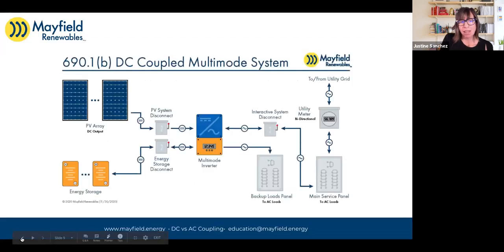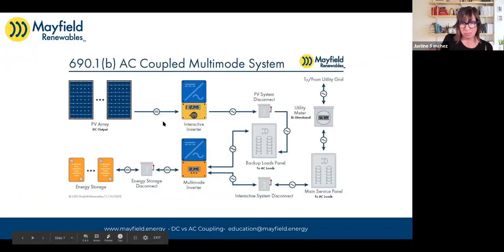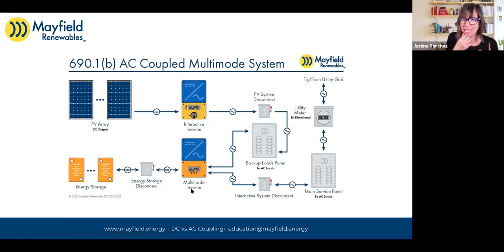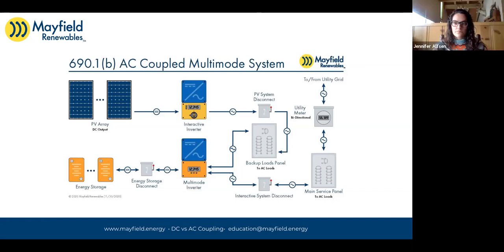And that is the idea that, okay, let's say the scenario arises. Let's go back to our AC coupled system where we didn't do a good job of telling our client how much energy they had available to them, and there's an outage, and they kept running everything they wanted to and then some in their backed up loads panel, and they got to the point where this energy storage got so low in voltage that it shut down this multi-mode inverter. Okay, because there's a minimum threshold that the inverter needs to see to operate.